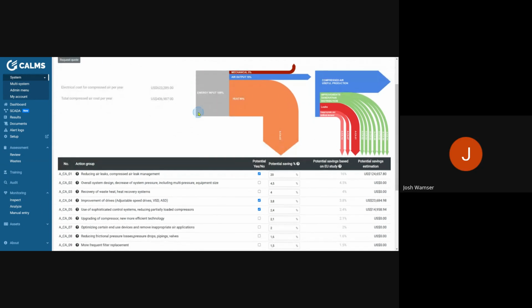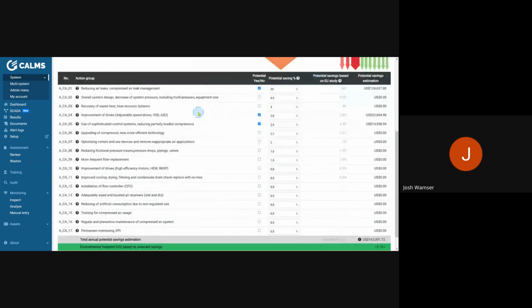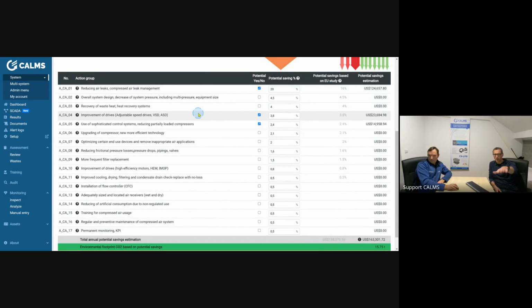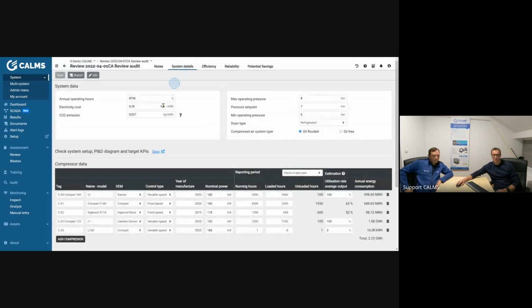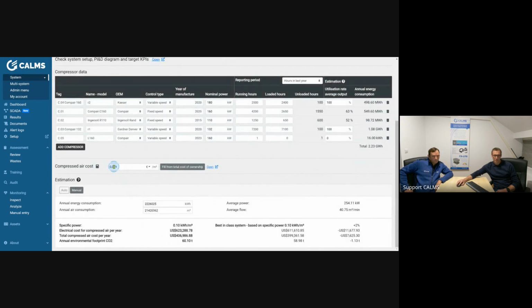You're at 623,000, and of course that's in American right now. Am I supposed to go up? I'm sorry. Yeah. 600,000 for electricity, and the total cost for the compressed air is 400,000. Obviously, you consume more air, or the cost of air is too low. It cannot happen that the compressed air cost is below the kilowatt hours cost. So maybe we have made a mistake here. You notice this correctly. So maybe the compressed air cost is not 0, but it's like this. Euro. Okay, this is euro. This may be the problem.